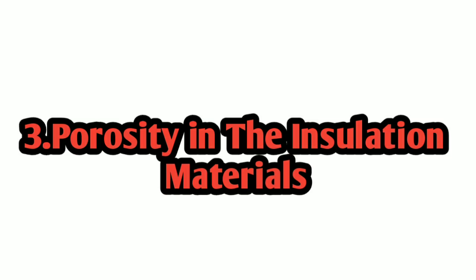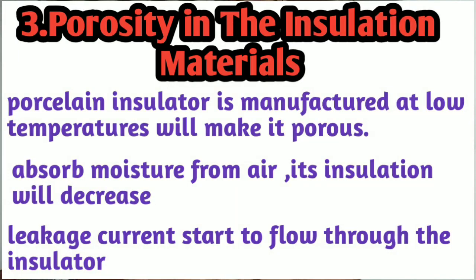Another cause is porosity in the insulators — pores forming in the material. The insulator is manufactured at a certain temperature. If during manufacturing the temperature is too low — say 120 or 150 degrees instead of the required amount — the material is not properly fired, and pores will form. These pores remain in the insulator material.